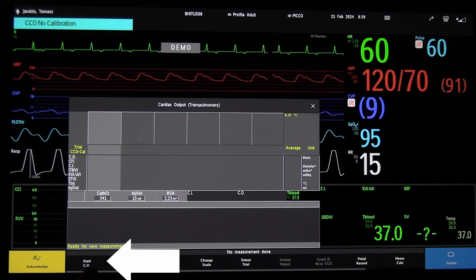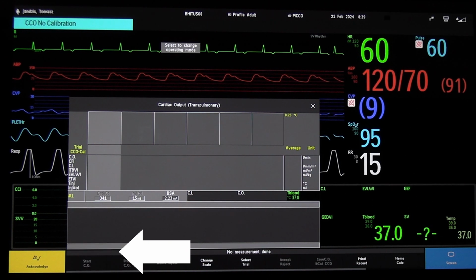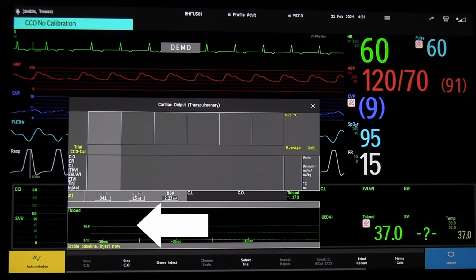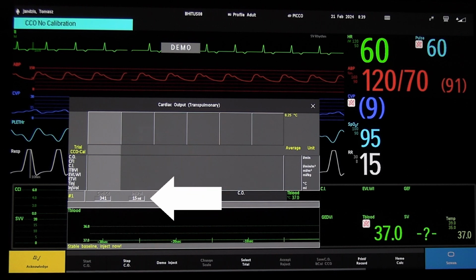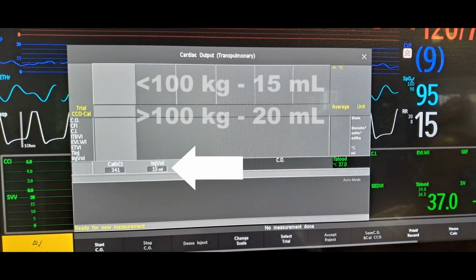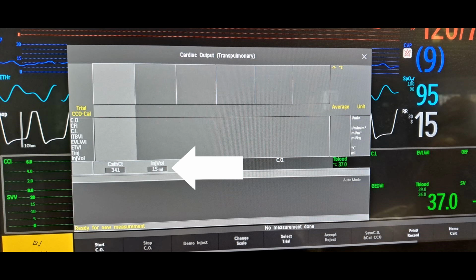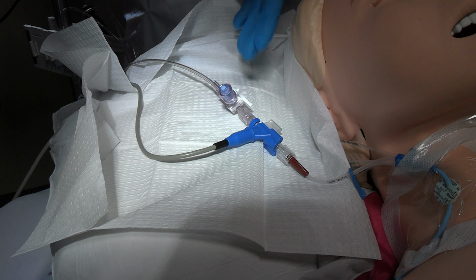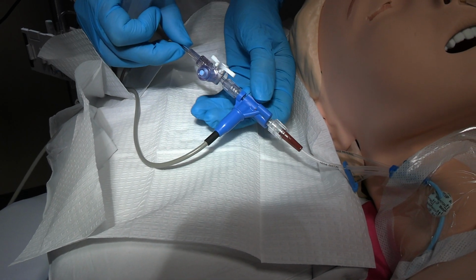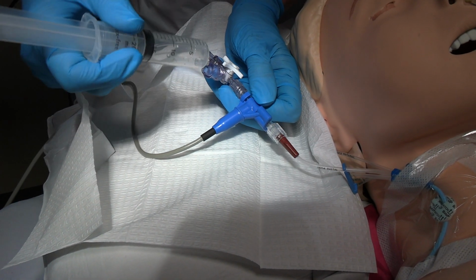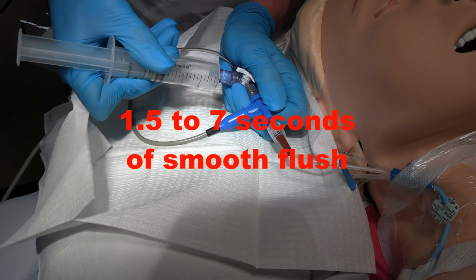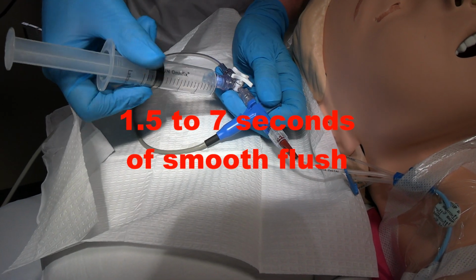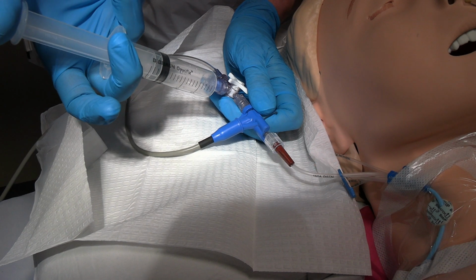Press the Start PiCCO button and await the prompt Inject Now. The volume to be injected is calculated by the monitor and displayed. If necessary, you can adjust the volume by touching the number according to the formula: 15 milliliters for patients below 100 kilograms and 20 milliliters for those above 100 kilograms. Inject the bolus of cold saline smoothly and quickly within 1.5 to 7 seconds, being careful not to warm up the injected volume with your fingers.